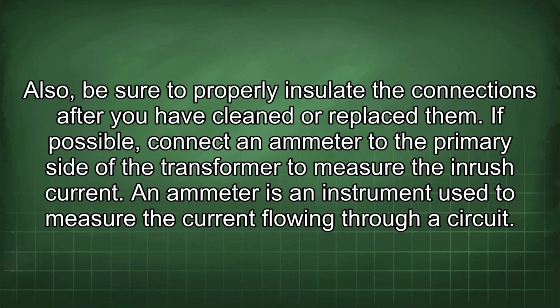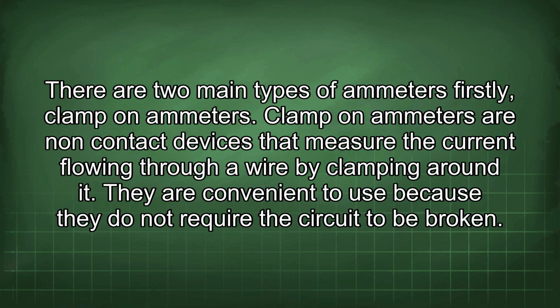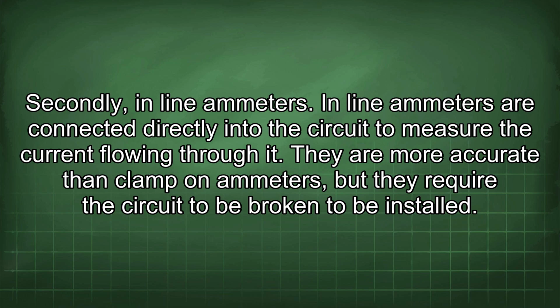If possible, connect an ammeter to the primary side of the transformer to measure the inrush current. An ammeter is an instrument used to measure the current flowing through a circuit. There are two main types of ammeters. Firstly, clamp-on ammeters. Clamp-on ammeters are non-contact devices that measure the current flowing through a wire by clamping around it. They are convenient to use because they do not require the circuit to be broken. Secondly, inline ammeters. Inline ammeters are connected directly into the circuit to measure the current flowing through it. They are more accurate than clamp-on ammeters, but they require the circuit to be broken to be installed.